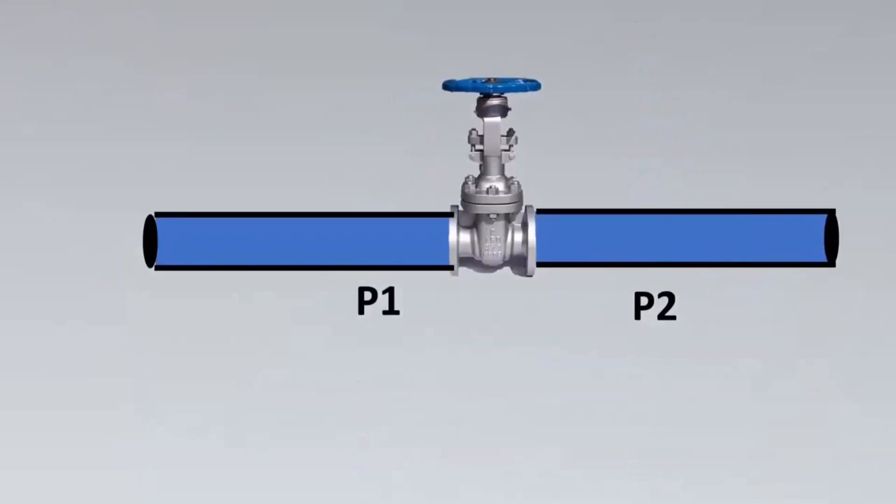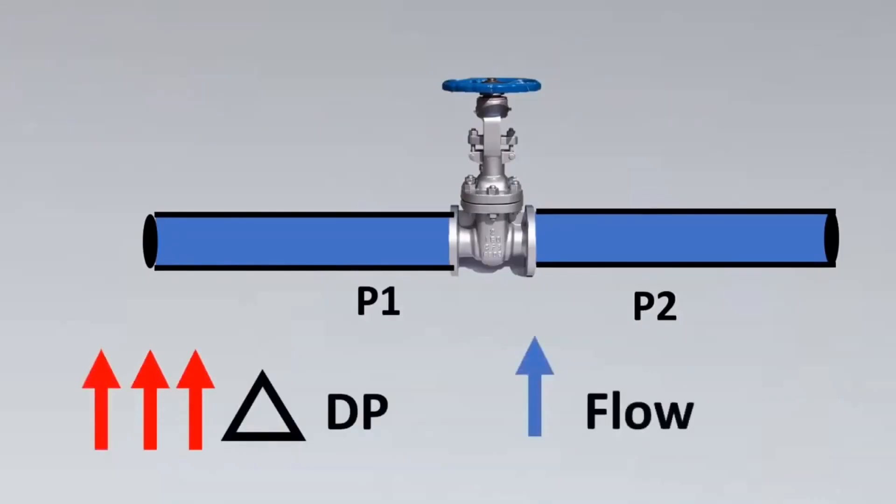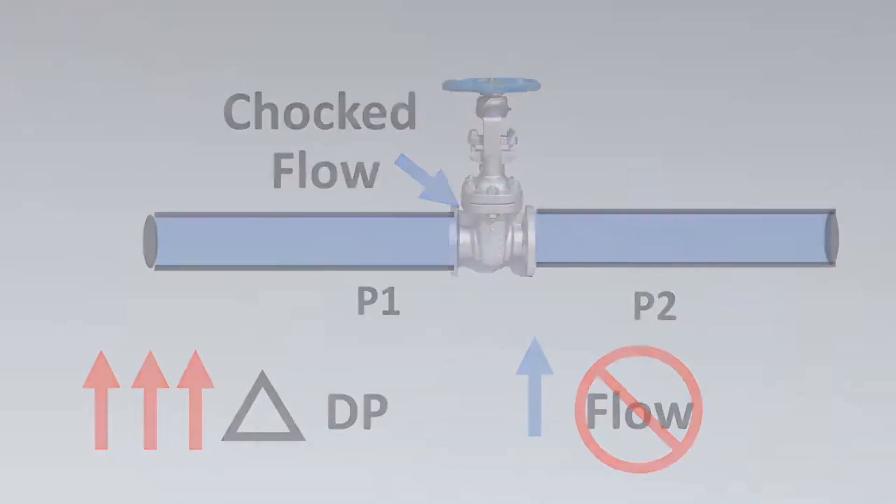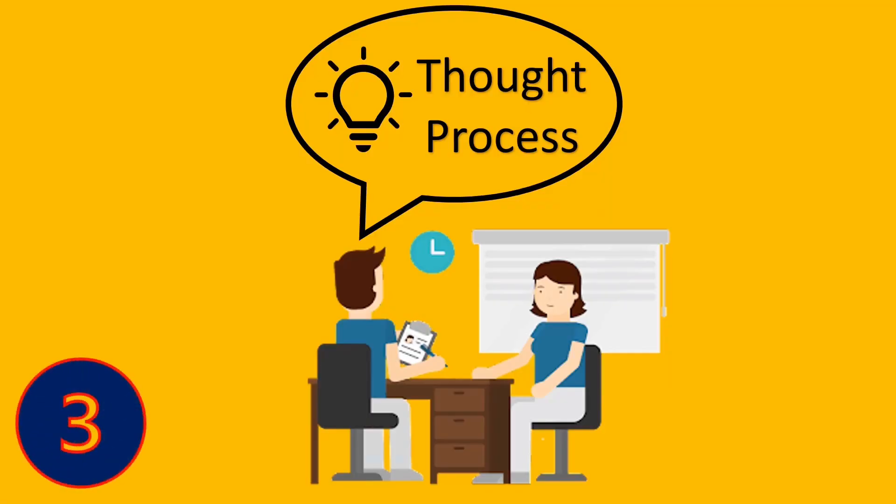Imagine this is your valve and this is your pressure drop happening. We are very sure that if we increase DP, there is going to be an increase in flow. But we keep increasing DP, at a point of time flow will not increase. This point is called choke flow.